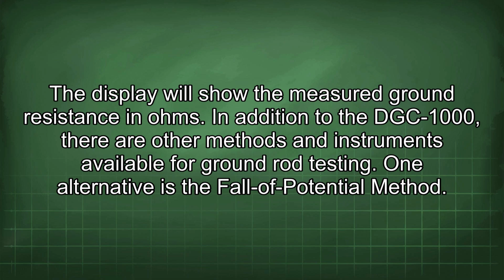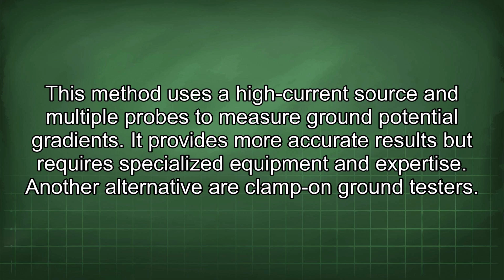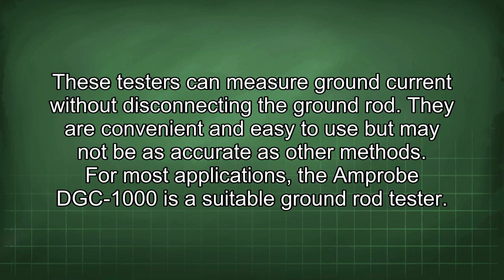In addition to the DGC-1000, there are other methods and instruments available for ground rod testing. One alternative is the fall of potential method. This method uses a high current source and multiple probes to measure ground potential gradients. It provides more accurate results but requires specialized equipment and expertise. Another alternative is clamp-on ground testers. These testers can measure ground current without disconnecting the ground rod. They are convenient and easy to use but may not be as accurate as other methods.